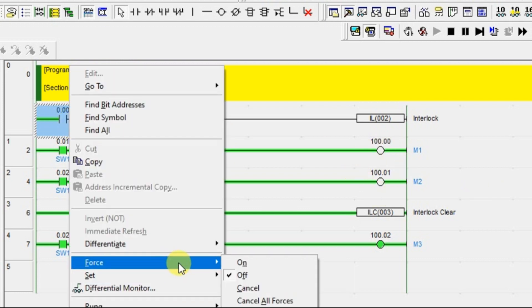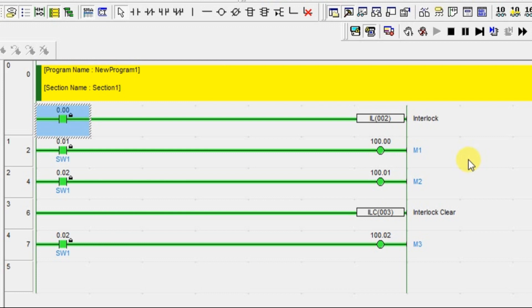See, if you again turn on your interlock, both the outputs will be in on condition. This is how you can protect your devices in emergency cases. CX programmer is having interlock, IL and ILC instruction for this feature. You can make use of it to protect your devices in critical conditions.